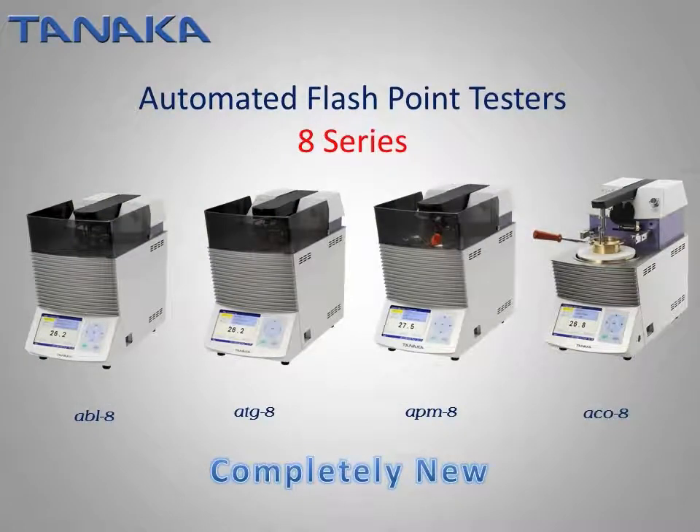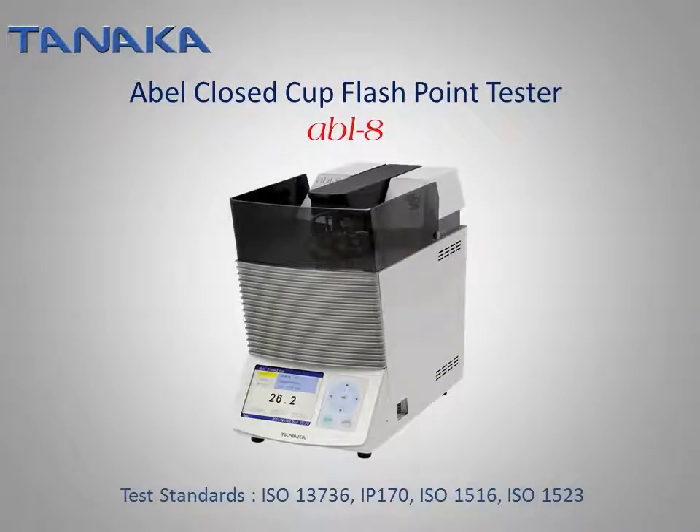Now let us explain the specifications of each flashpoint tester. The Abel closed-cup flashpoint tester, model ABL-8, conforms to ISO 13736, IP 170, ISO 1516, and ISO 1523. Two models for different temperature ranges are available: the ABL-8A is an air-cooled model covering 10°C to 110°C, and the ABL-8L is a liquid-cooled model covering -30°C to 110°C. The ABL-8L is used with an optional chiller unit.